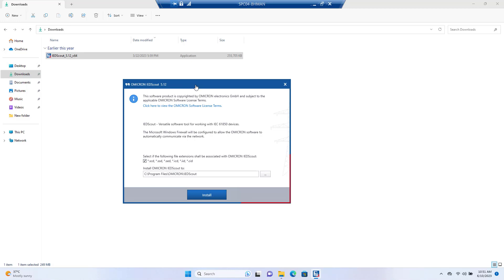On the pop-up, by selecting the IED Scout installation, you get an overview of whether you want to use the IED Scout software application for different types of SCL files, part of the IEC 61850 standard. We have system-specific files and IED-specific files — these are file formats from different IED configuration tools, system configuration tools, or system specification tools. When you have an SCL file on your PC, by default the IED Scout icon is applied when you enable this option. If you do not want to open those file extensions by default with IED Scout, you can uncheck it. I would like to open all different types of SCL files with IED Scout, so I enable this option.